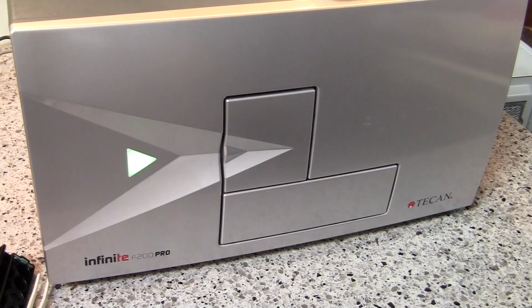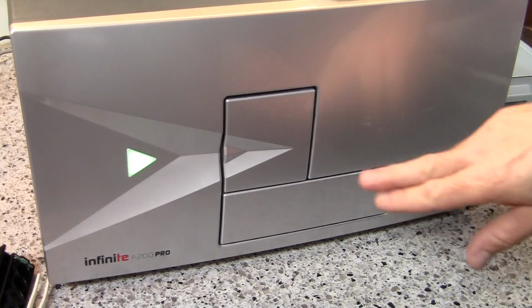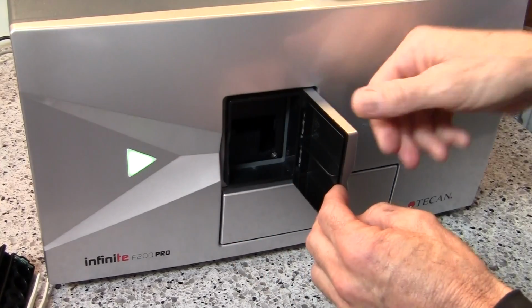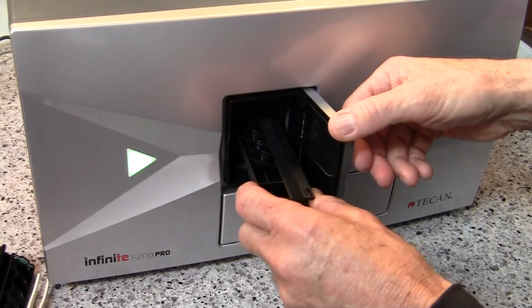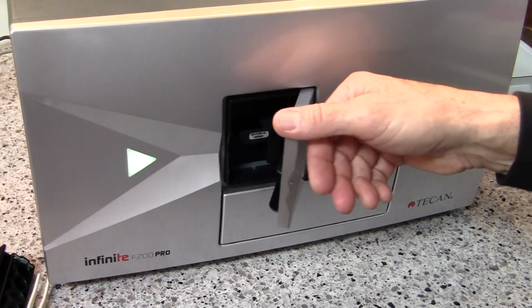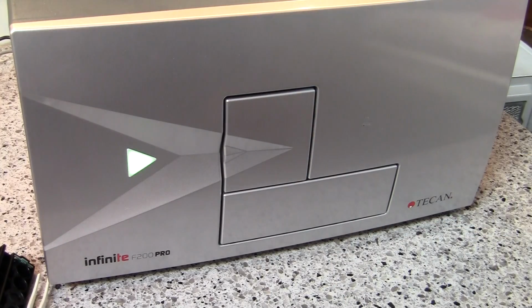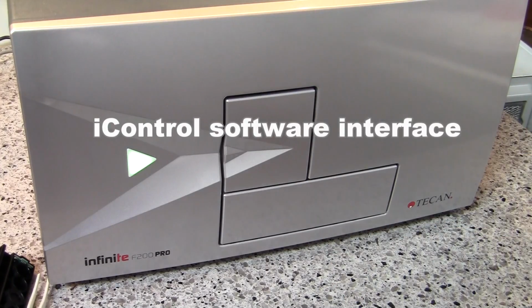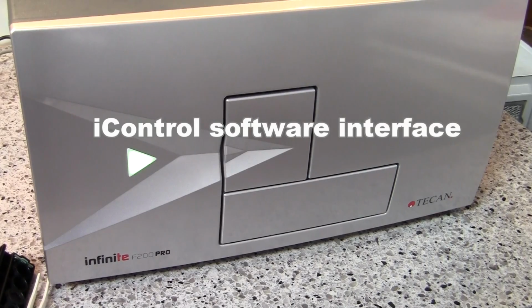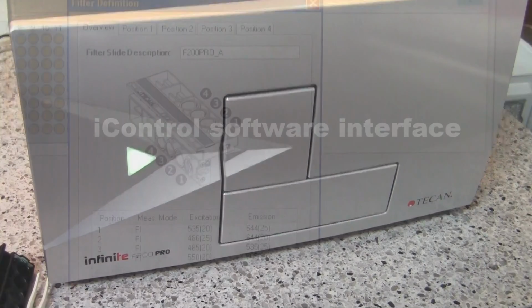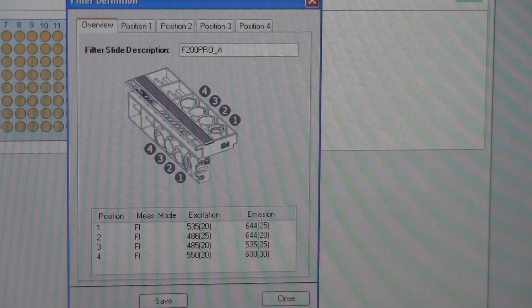Once you've installed your filters, you're going to want to place that filter holder in the instrument. Open the door here, slide the filter in, let the instrument grab hold of it, and it will drag it in. From there, go to the software, into settings under filter definitions, and change the definitions of the filters for each of the four positions where you've installed filters or not. In the filter definition window, step through each of the tabs for position 1, 2, 3, and 4 and program what type of filter is there.